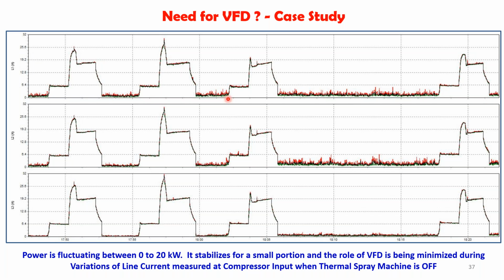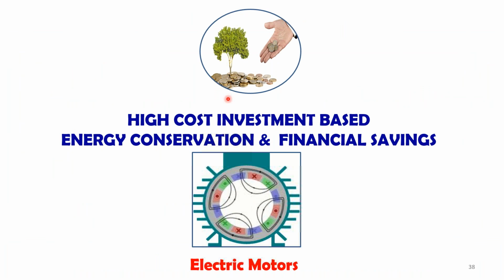So we requested the company to investigate whether the VFD is required or not, or whether you have a higher capacity machine where a VFD application makes sense. Again, I told you, you have to inspect whether a VFD is required or not. I think Nagesh Kumar sir always told you that VFD is not a magic box. It will not give you a saving all the time. It will give saving for one application, but not for other applications. So the requirement has to be properly analyzed. Then only can you suggest retrofitting the VFD, or buying new equipment with a VFD, based on your requirement and operating conditions. So that's the point I want to tell you.